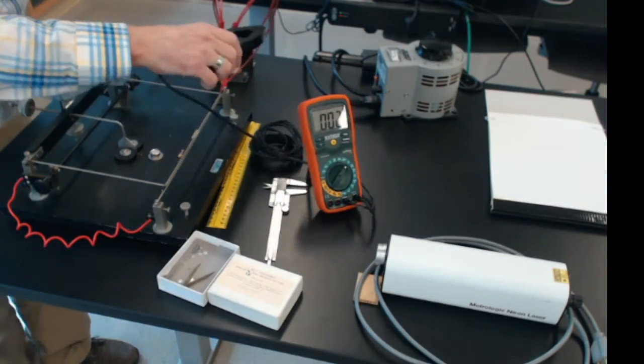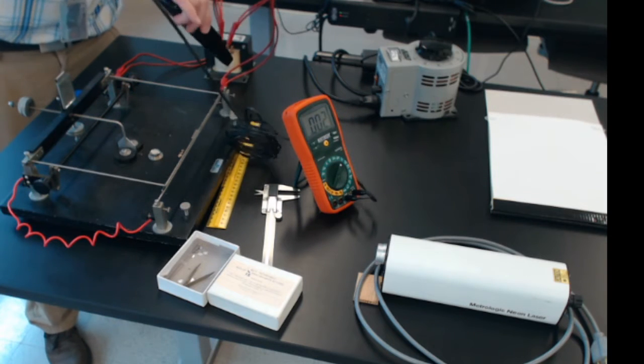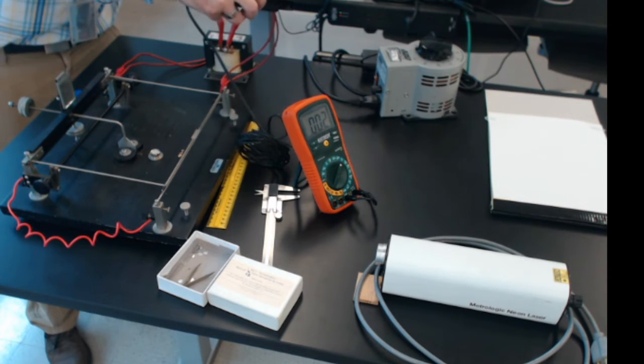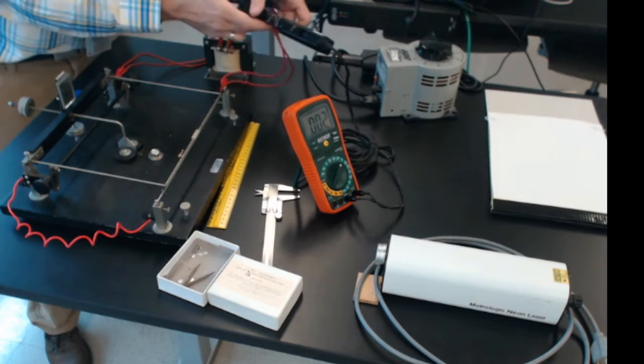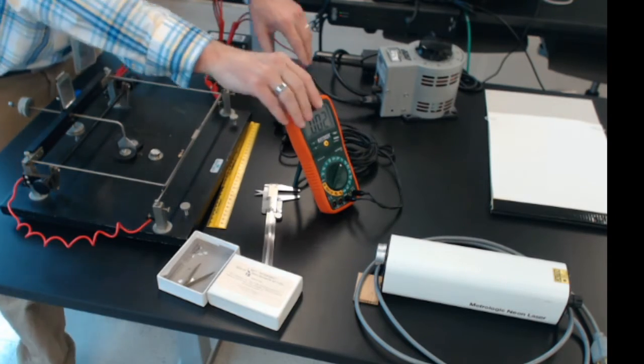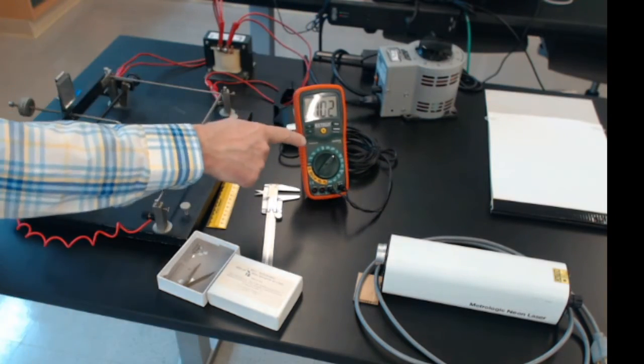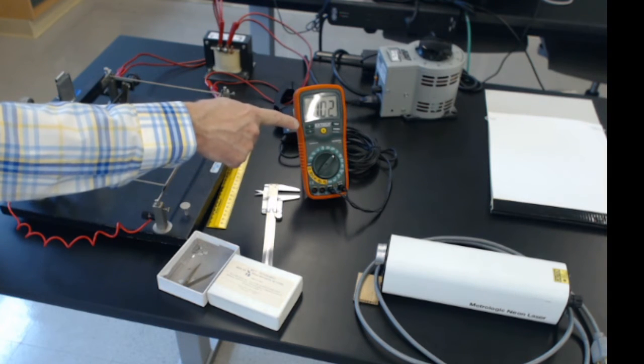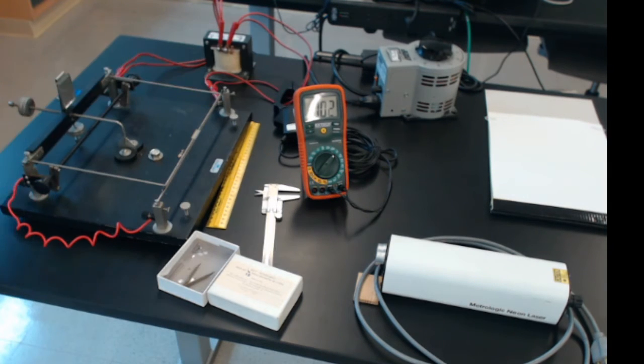So that's how we'll measure the current. And then the amp clamp. Let's see, we'll take the wires that carry the current through the wires. We'll just put the amp clamp so that the wires go through here. And now we're set up to measure the current through the wires by measuring the voltage from the amp clamp. Okay, what else have we got here?